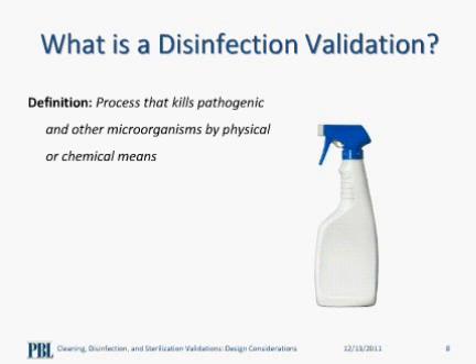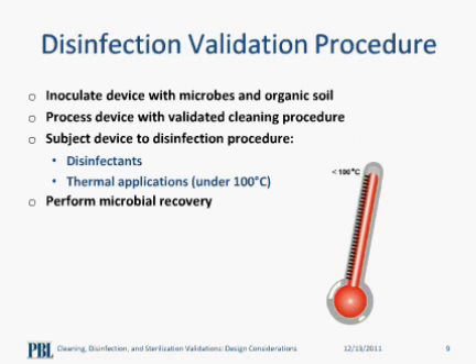Now that the cleaning procedure is validated, the device can be subjected to the next step in reprocessing, which can be disinfection or sterilization, depending on your device. But first, we can cover what a disinfection validation is. As a reminder, disinfection is the process that kills pathogenic and other microorganisms by physical or chemical means. In order to validate a disinfection procedure, we first inoculate the device with representative microbes and organic soil. Then we clean the devices with the previously validated cleaning procedure before subjecting the devices to a proposed disinfection procedure using disinfectants or thermal applications, generally with the use of water under 100 degrees Celsius.